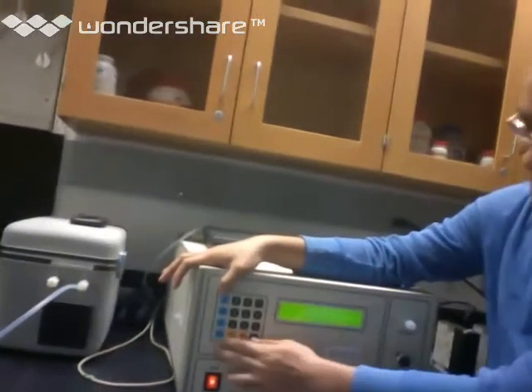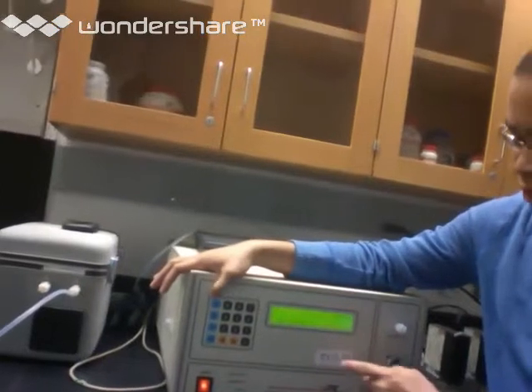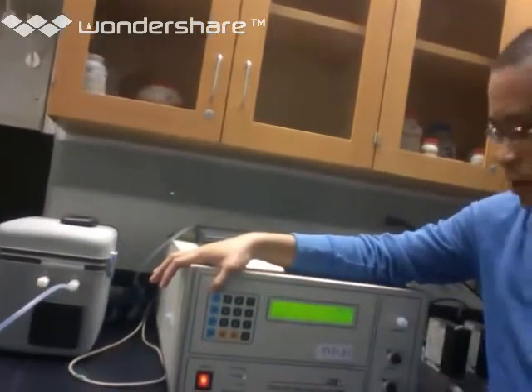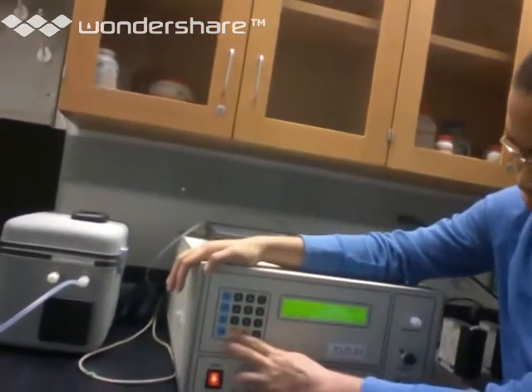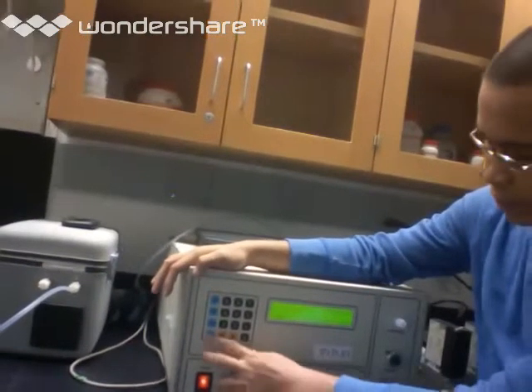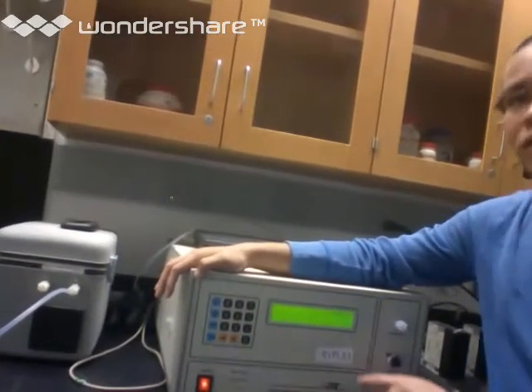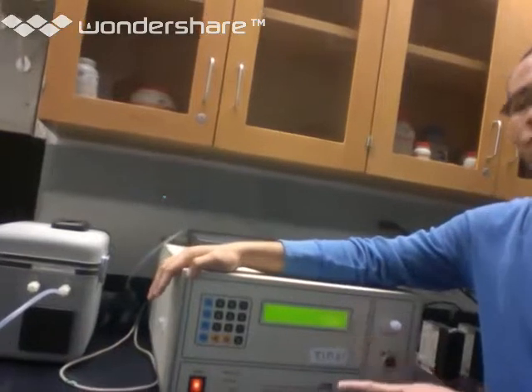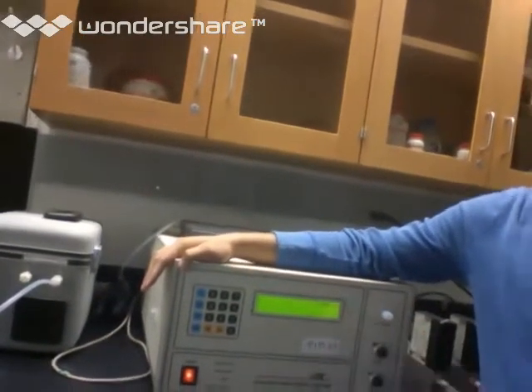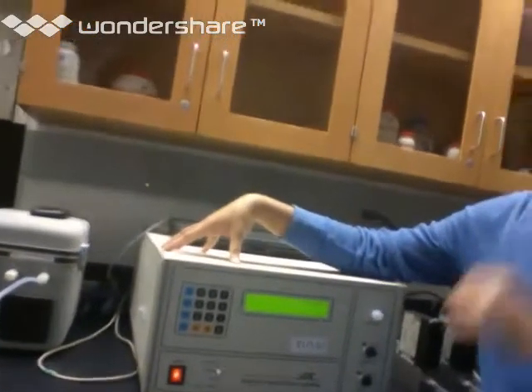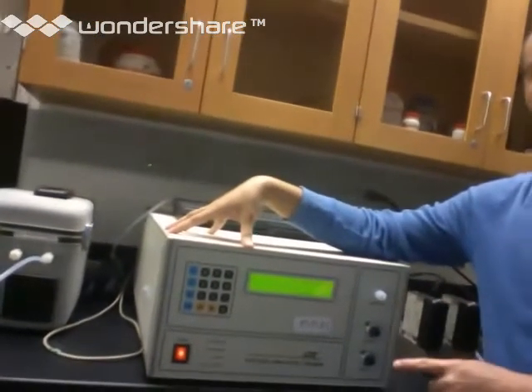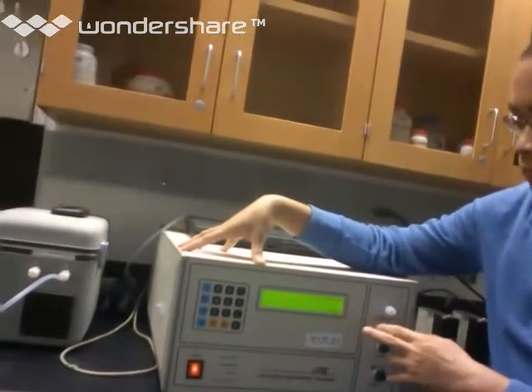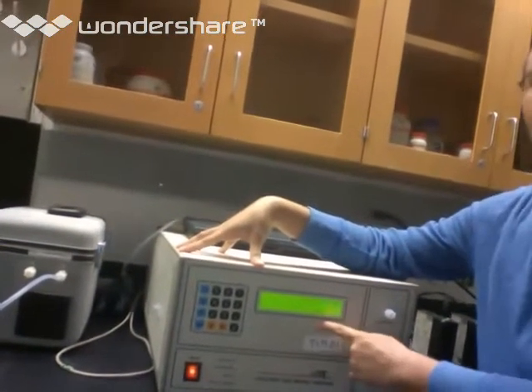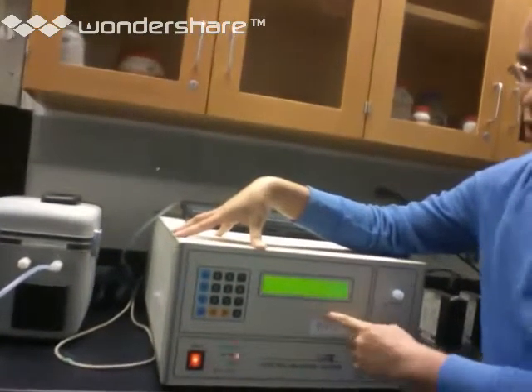You want to actually go into calibrate, which is the first option under the main menu. Once you're in the calibrate menu, you want to navigate to type. The default is always source. That just means it takes it from the perm source. So our daily calibrations, this calibrates automatically daily. So it'll actually calibrate using its own internal source, which functions much like that one. But we're going to do an injection calibration right now. So we're going to switch it to inject.